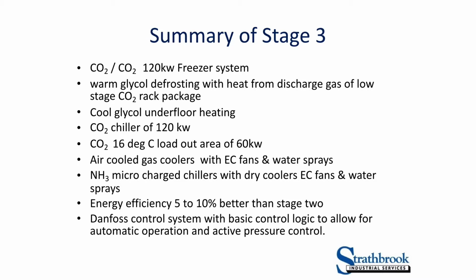So our summary of stage 3, basically the same CO2 system with our 2 packages cascaded together, but now the cool rooms are on a separate CO2 package because the scale of the place was bigger. We've gone to an ammonia chiller instead of a freon chiller, which has nearly 3 times the COP. Gas coolers with EC fans and water sprays to drag some more energy efficiency into the process.